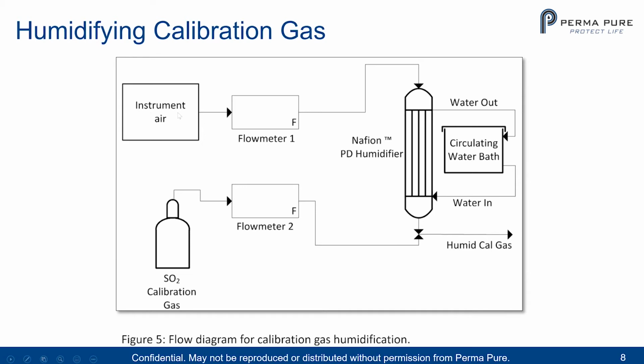So what we did here is we took our instrument air, and first, this is very important, we humidified the instrument air with a humidifier using water to gas humidification. That allows us to get a very efficient and a very high level of water vapor into this gas. And then we mixed it with the calibration gas in the vapor phase, and you can see that down here. We did that on purpose because we were able to control precisely how much water we wanted in the gas. We also did not want to humidify the gas directly with water because we found that you will get some losses that way. So we first humidified the air that was going to be used to mix with the calibration gas to get us our test gas.